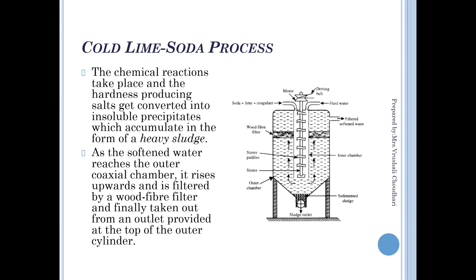In the cold soda-lime process tank, when soda and lime are added from the top they pass down and mix with the hard water — which contains calcium and magnesium salts — forming an insoluble precipitate. Initially the hard water contains soluble salts which are converted into insoluble precipitate. Since the precipitate is heavier than water, it settles at the bottom and is removed via the sludge outlet, while purified softer water is collected from the upper outer outlet through a wood-fiber filter.